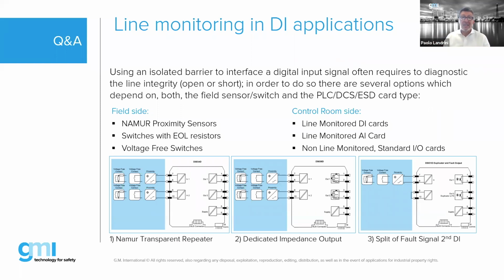When you have a card that is non-line monitored, so cannot read this information, then you have to duplicate the signal. You can see in the third drawing here, and split the signal, one as your on-off and the second as alarm, and detect this through a second DI contact. I hope I was clear. I tried to move fast. The time is moving.